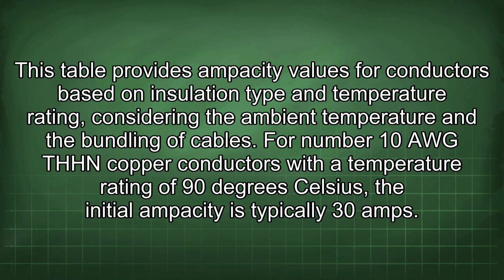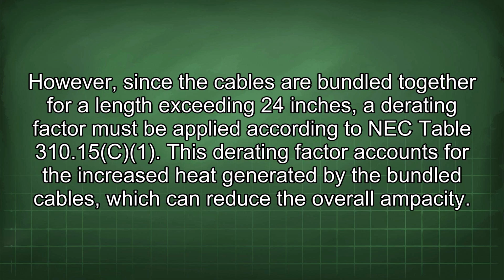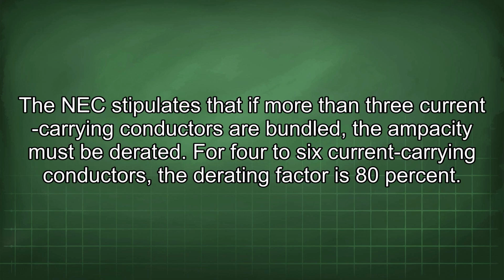For number 10 AWG THHN copper conductors with a temperature rating of 90 degrees Celsius, the initial ampacity is typically 30 amps. However, since the cables are bundled together for a length exceeding 24 inches, a derating factor must be applied according to NEC Table 310.15(C)(1). This derating factor accounts for the increased heat generated by the bundled cables, which can reduce the overall ampacity. The NEC stipulates that if more than 3 current carrying conductors are bundled, the ampacity must be derated. For 4 to 6 current carrying conductors, the derating factor is 80%.